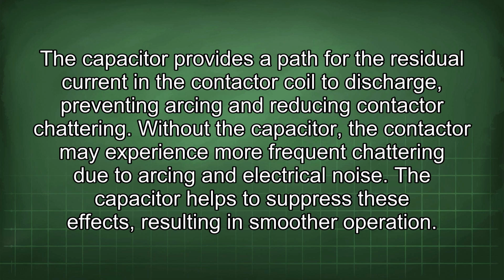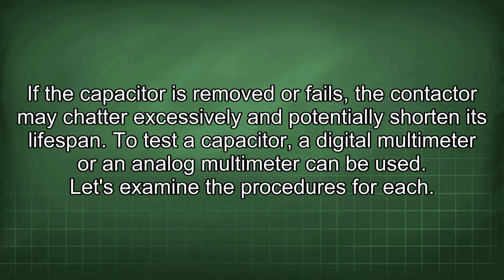The capacitor provides a path for the residual current in the contactor coil to discharge, preventing arcing and reducing contactor chattering. Without the capacitor, the contactor may experience more frequent chattering due to arcing and electrical noise. The capacitor helps to suppress these effects, resulting in smoother operation. If the capacitor is removed or fails, the contactor may chatter excessively and potentially shorten its lifespan.